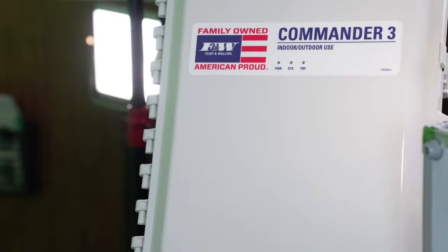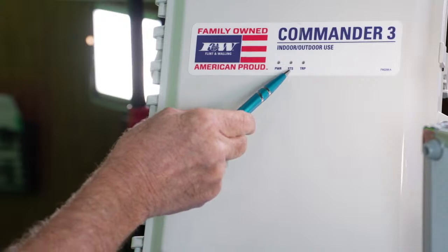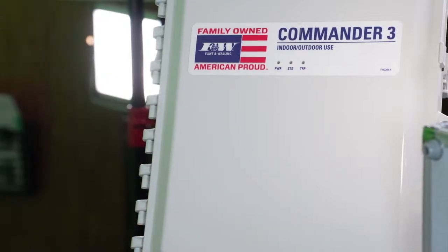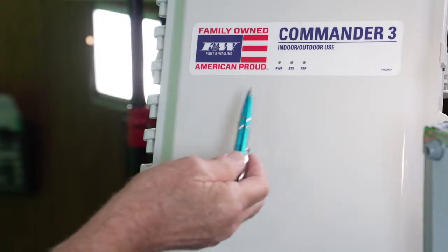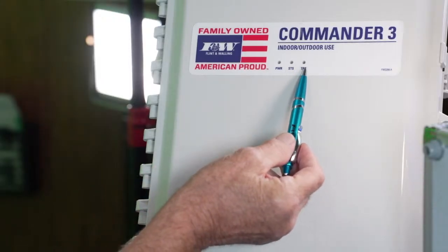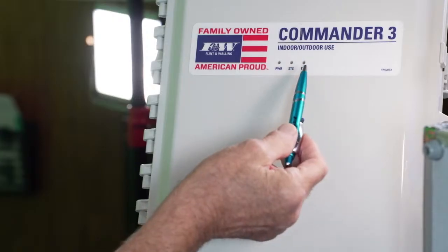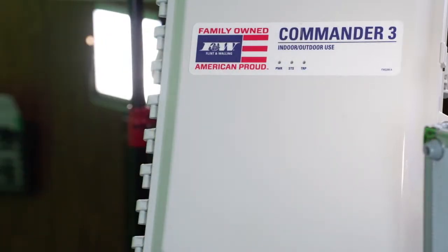The next light, which is referred to as the status light, I think everybody can probably see that. That's located right there. That light can be solid or blinking. Dependent on whether that's solid or blinking, that's going to give us the status of this drive. And then the last one over here on the far right is the trip light. Again, that's a light that's either solid or blinking, and based on what that's doing, it is also going to give us an indication of why this drive may have tripped out.